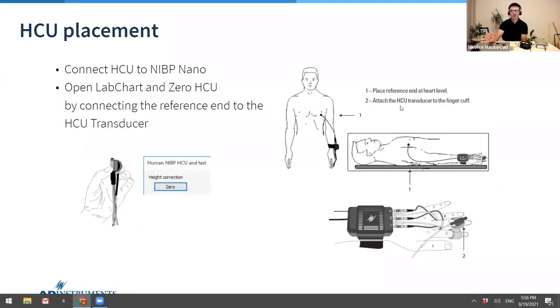A bit more about the application and how the HCU works: the first thing to do is zero the HCU unit. What I'm going to show you is that we connect the transducer and the reference end together, and in the software, we click in the NIBP settings to zero this. That way they're at the same level. Once that's done, we can simply connect the transducer to the finger cuff and have the reference end somewhere around the heart level. That way the pressure will stay at a stable reading. You can see the subject here has a reference end here. That's fairly simple to use. Obviously that's going to compensate whether you move up or even further down as well.